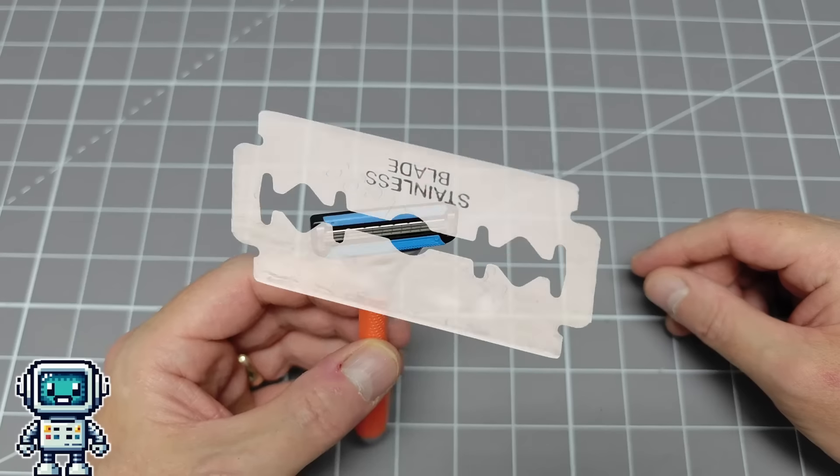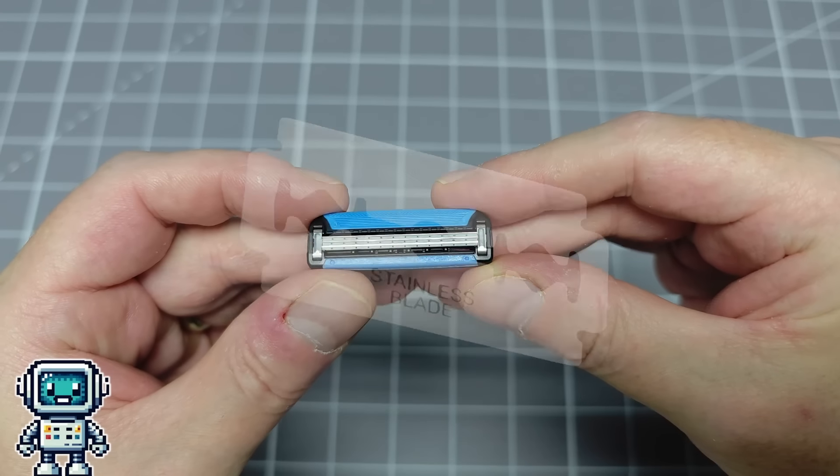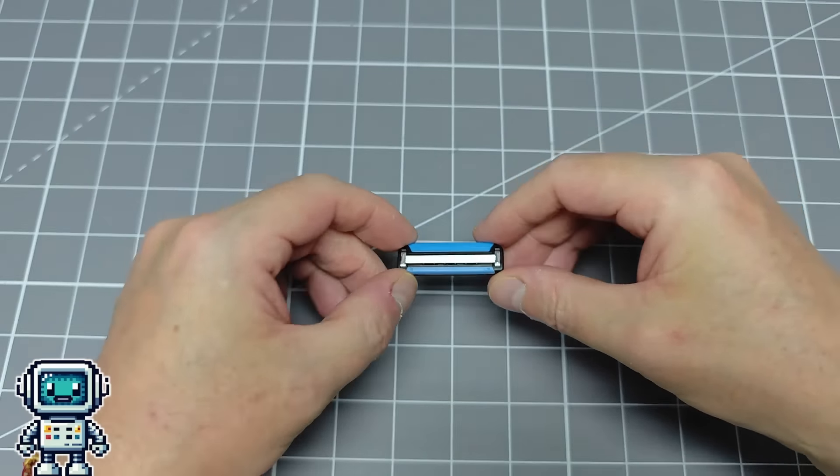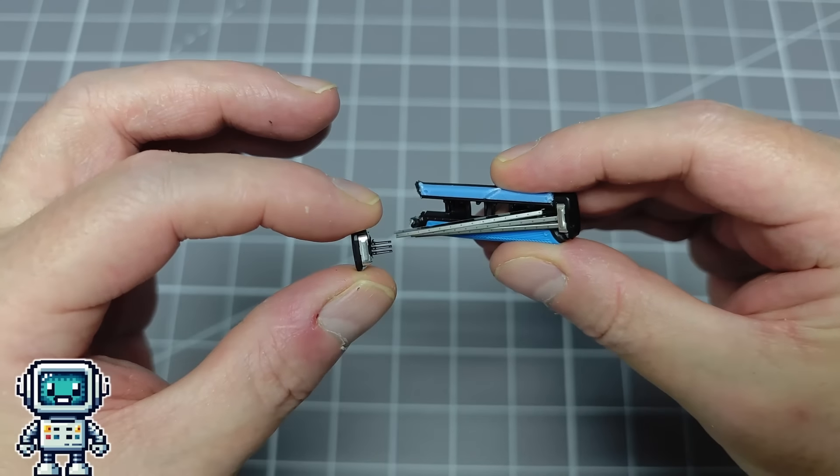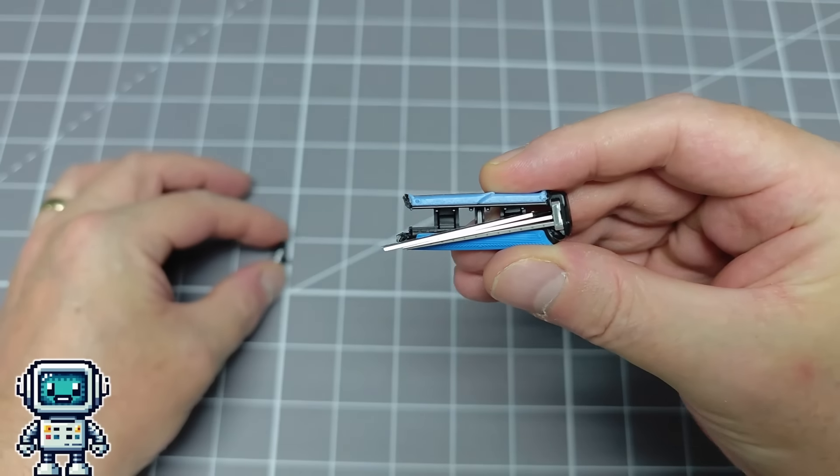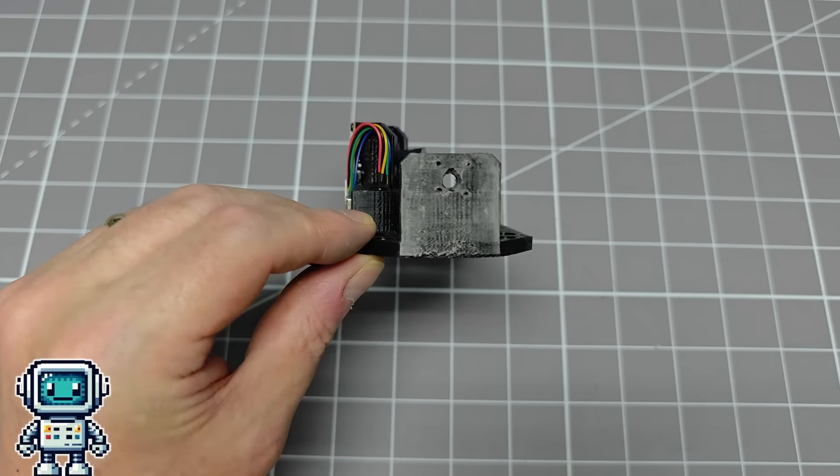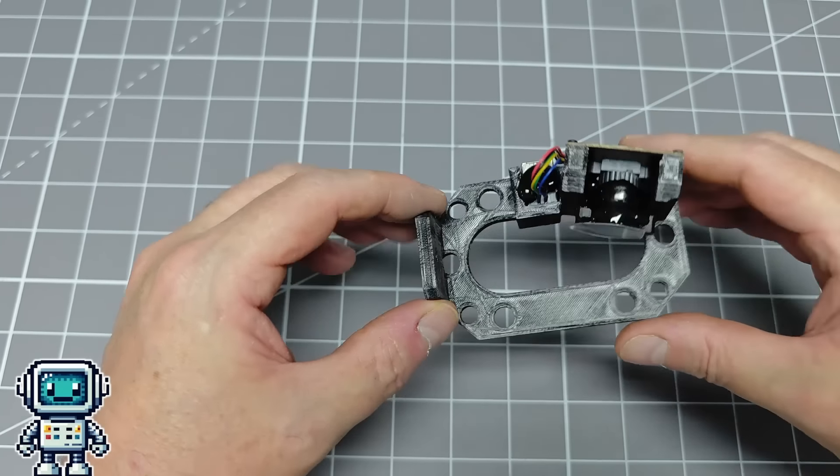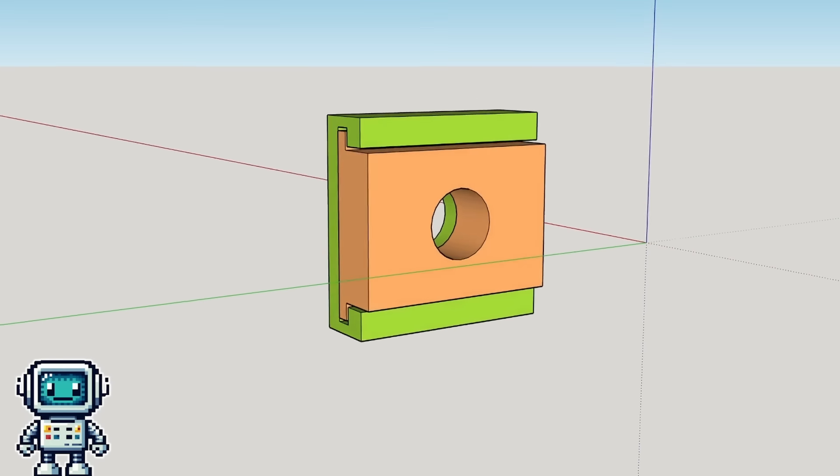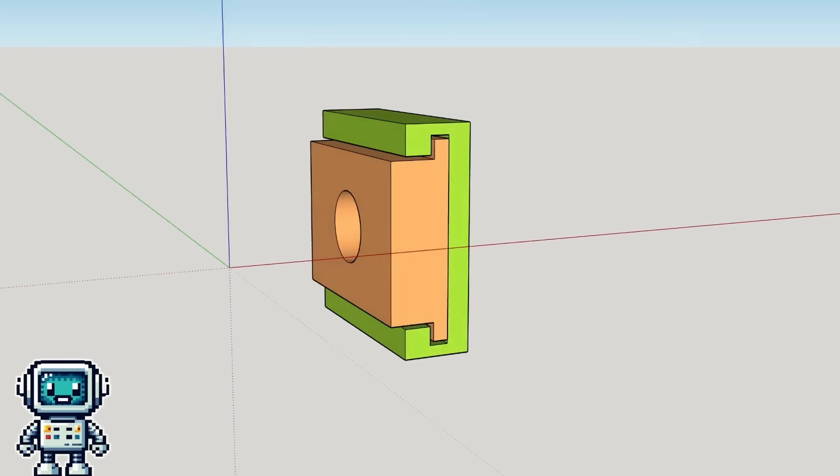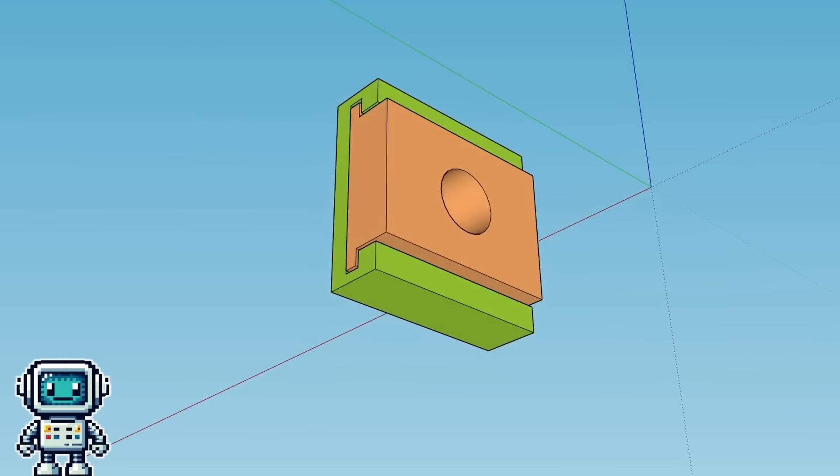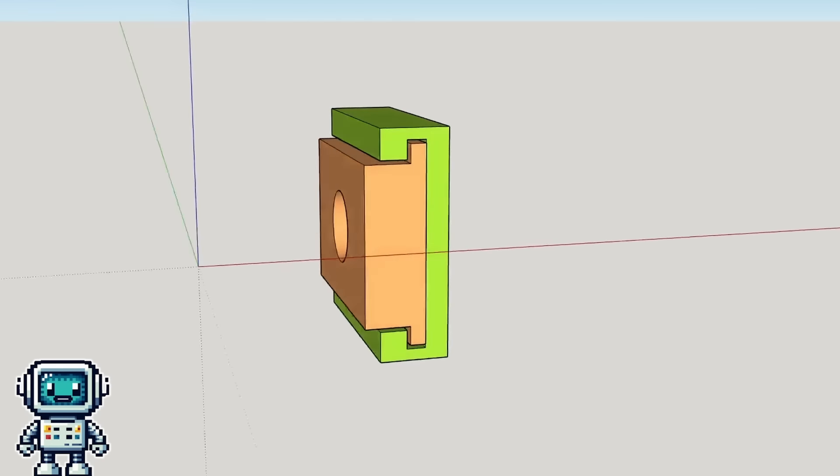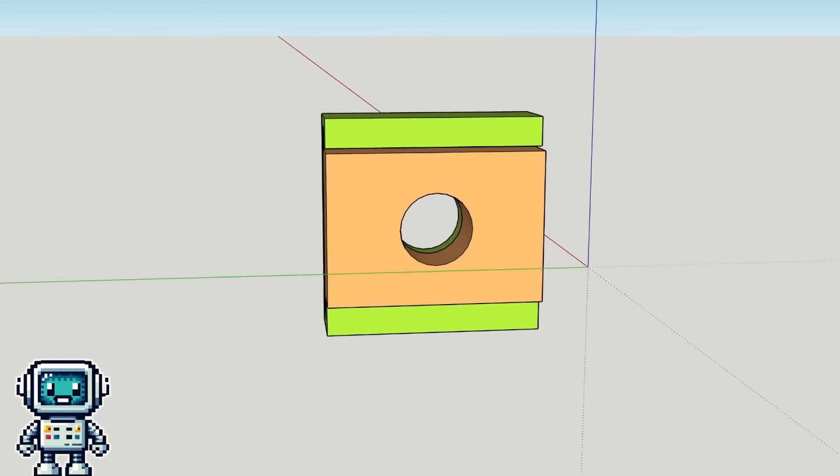We can't buy those types of old-fashioned razor blades here in China, so we thought we would try using the blades from a disposable razor. After removing the blades from the razor, we got on and drilled out the old 3D printed slit. We figured that we would make a special slit holder to allow it to be correctly aligned after assembly. The green part is permanently attached to the spectrometer chassis and the orange part has the custom slit attached to it. In this way the alignment can be adjusted.